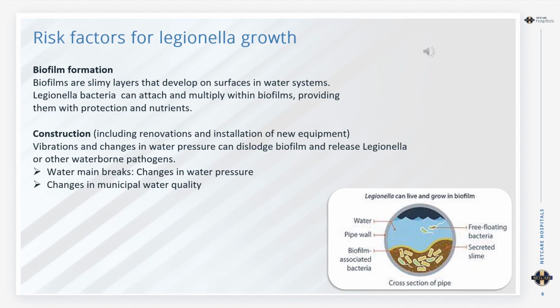During construction, including renovations and installation of any new equipment, vibrations and changes in the water pressure can dislodge biofilm and release Legionella or other waterborne pathogens. This can happen when there are any water main breaks, so there are changes in the water pressure or changes in municipal water quality. Therefore, we suggest if there are any repairs or work done on lines or pipes at facility level and where there is water interruption, flushing lines for a longer period once the work is completed.